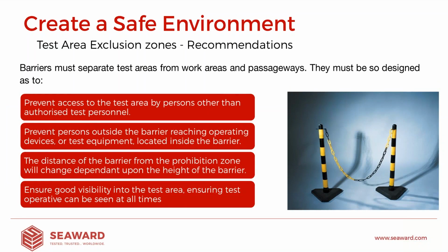We can then look at the external protection, so how we keep people away from the test area. And we do that by creating exclusion zones. Now, exclusion zones can be very, very simple. They can be a simple post and chain link to specific test cages. But essentially, the idea of an exclusion zone is to prevent access to the test area by anyone that's not trained to be in there. These barriers should be sufficiently far away from the product under test so that the person cannot effectively reach in and touch the product during the test.